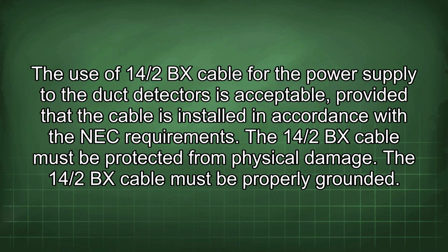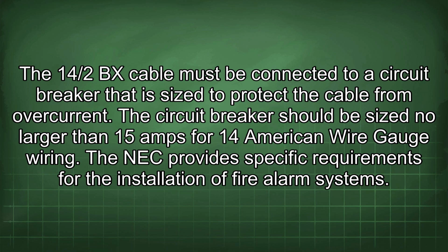The use of 14/2 BX cable for the power supply to the duct detectors is acceptable, provided that the cable is installed in accordance with the NEC requirements. 14/2 BX cable must be protected from physical damage. The 14/2 BX cable must be properly grounded. The 14/2 BX cable must be connected to a circuit breaker that is sized to protect the cable from overcurrent. The circuit breaker should be sized no larger than 15 amps for 14 American wire gauge wiring.